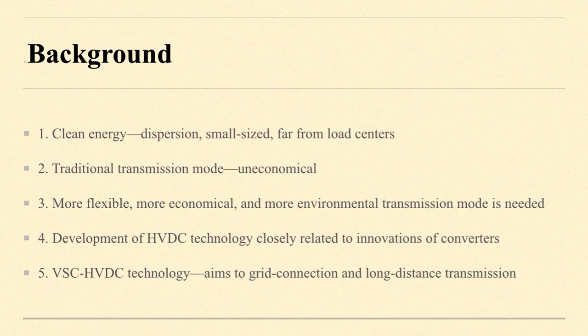Firstly, the background. As for clean energy, dispersion, small size, and distance from load centers are inherent characteristics. Traditional transmission modes, AC transmission systems for instance, are actually uneconomical. A more flexible, more economical, and more environmentally friendly transmission mode is needed. The development of high voltage DC (HVDC) transmission technology is closely related to innovations in converters. In 1990, DC transmission based on VSC converters was first proposed. Nowadays, many researchers have studied many aspects of VSC HVDC transmission systems, but researchers limited to a single field cannot achieve breakthrough improvement.